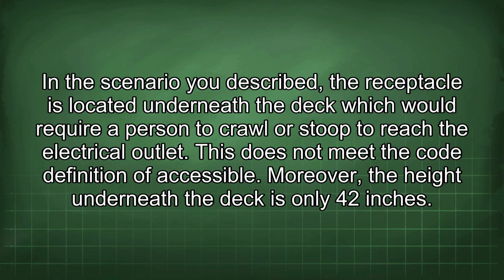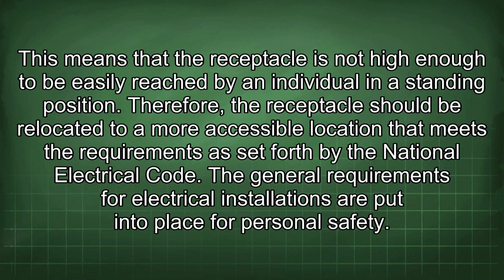In the scenario you described, the receptacle is located underneath the deck, which would require a person to crawl or stoop to reach the electrical outlet. This does not meet the code definition of accessible. Moreover, the height underneath the deck is only 42 inches. This means that the receptacle is not high enough to be easily reached by an individual in a standing position.